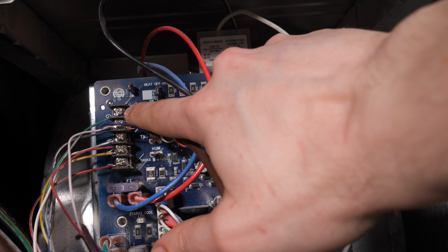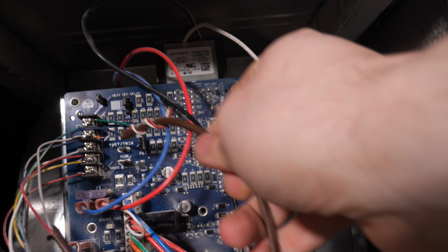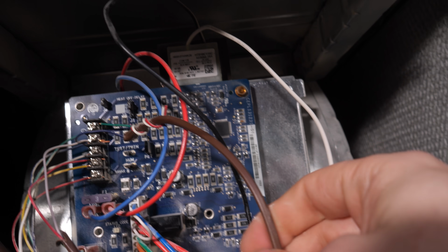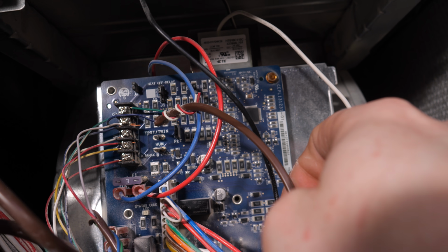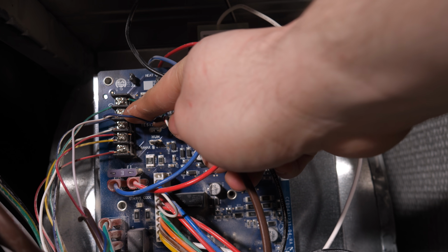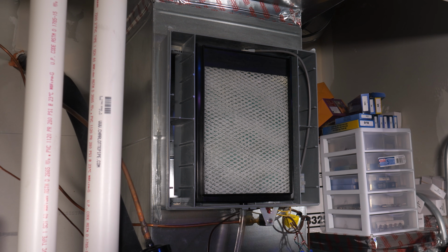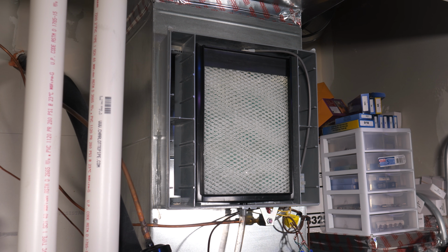Instead of hooking the humidifier's water valve to the heat signal wire, I changed it to the fan signal wire. This meant the humidifier was able to run so long as my thermostat was calling for the blower fan, and by setting a fan schedule on my thermostat which ensured the fan ran for 15 minutes every hour, my humidifier was actually able to do its job. And for the last couple of years, I've been enjoying delightfully moist air in the winter, nice and comfy and free of static shocks. This scenario is why the manufacturer wants this thing hooked to heat.